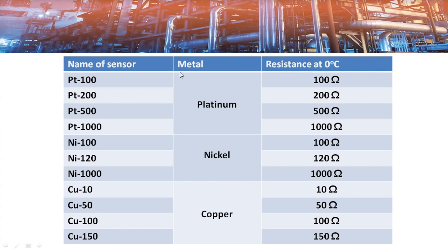Here you can see the different RTD sensors for these three metals: Platinum 100, Platinum 200, Nickel 100, Nickel 120, and Copper 100. These sensors are used for different applications, and the number in the sensor name indicates the resistance at 0°C. For example, Platinum 100 has 100 ohms and Platinum 1000 has 1000 ohms at 0°C.